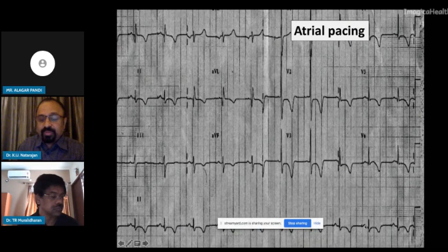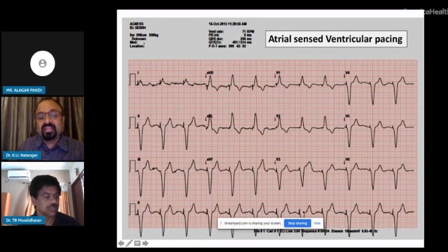The ECG gives a clue about the chamber paced, which I've already covered. If there's a spike followed by a P wave, like in this example, it's atrial pacing. If the spike is followed by a QRS, it's ventricular pacing. If there is atrial sensed ventricular pacing, then for every P wave you have a spike with a fixed AV interval. Obviously, it cannot be a VVI pacemaker. A VVI pacemaker has nothing to do with the preceding atrial activity, because there will be complete AV dissociation in a VVI pacemaker. Here, there is AV association. So a ventricular pacemaker that responds to the P wave with a fixed AV delay means atrial sensing is happening, so it cannot be a VVI pacemaker. This is an example of a dual chamber pacemaker.